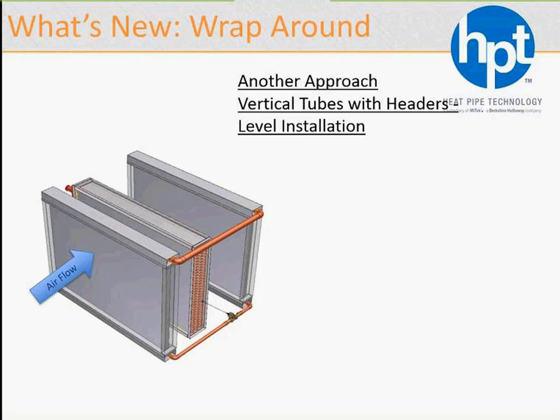What you're looking at here is the pre-cool, where the air is coming in, and the reheat on the other side. The tubes are vertical, fins would be horizontal. Vertical tubes allow us to construct headers at the very top and the bottom, and each header has a tube going from one side of the heat pipe, pre-cool, to the reheat. The upper pipe is the vapor line, and the lower one is the liquid line. You see in the liquid line, there's a valve, and this valve will help control the flow of refrigerant, consequently the performance of the heat pipe.